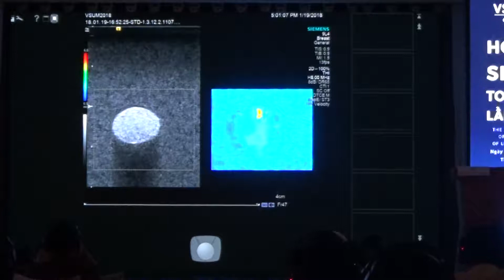The default is usually 6 or 7, depending on the probe, but if your measurement comes back as 'high,' you can change the maximum velocity so it falls within the scale. This is the velocity map — I'll increase the value so the colors look a bit different. We also have the quality map.